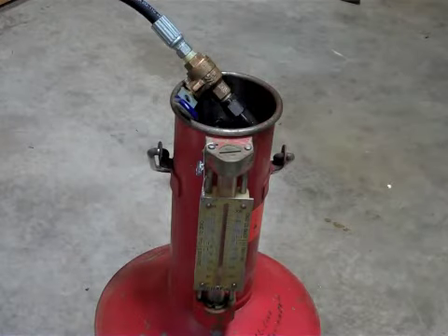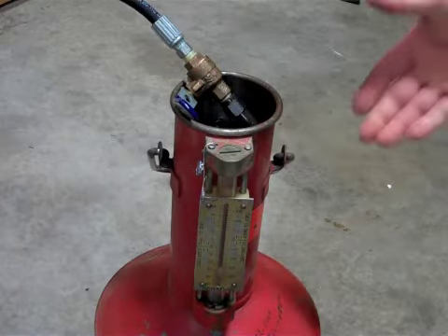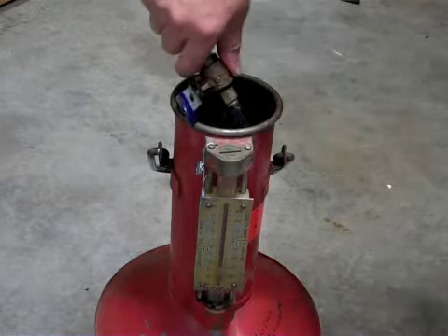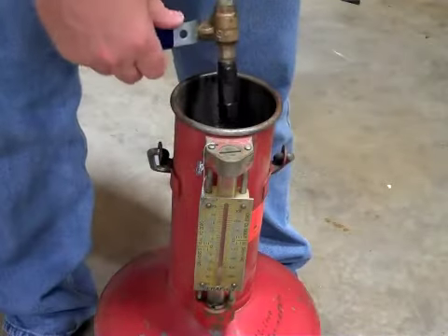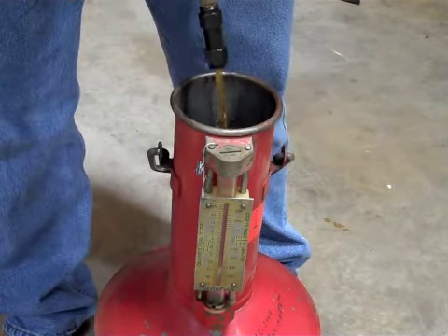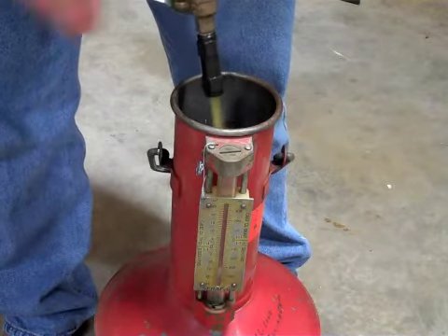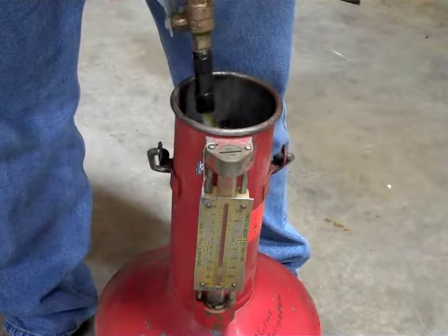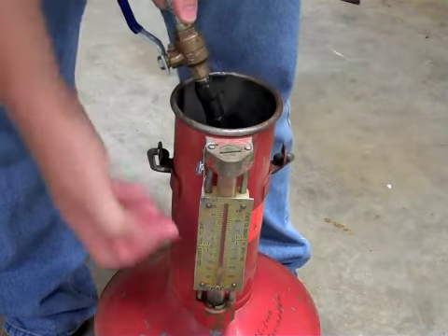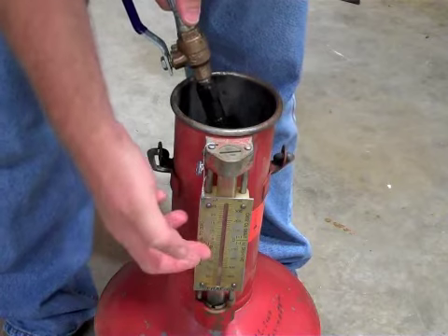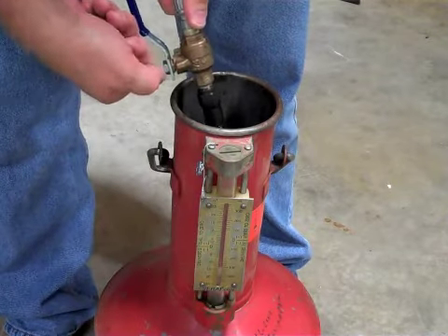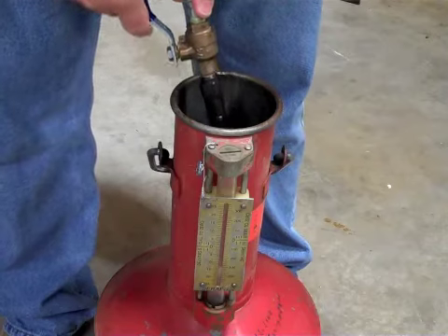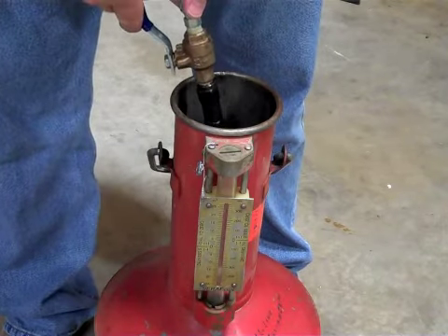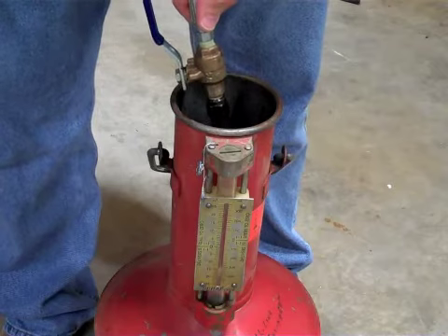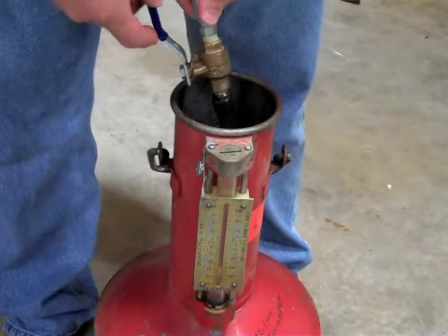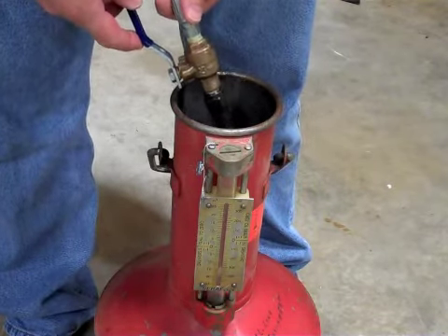Okay, what you hear is the pump running, so it's a little noisy. This is the calibration can, and we've started the pump, and we're going to dispense now into the calibration can. We're controlling the flow with this valve, so we're going to let it pump until we get to exactly 5 gallons here. Then we'll shut off the valve, and then we'll go back to the controller and finish our calibration. You want to make sure your hose has already had fluid run through it, so everything's wet. Of course, if you've done calibrations before, you're familiar with all that.